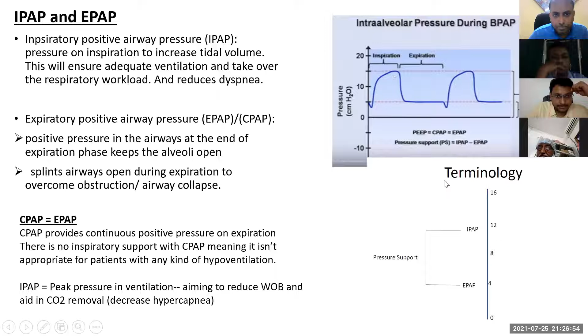So EPAP is maintained throughout the breathing cycle, and then extra pressure comes during the inspiration that drives the tidal volume. So tidal volume is dependent on the pressure difference between IPAP and EPAP. Okay, here also see, pressure support is equal to IPAP minus EPAP. Clear now?